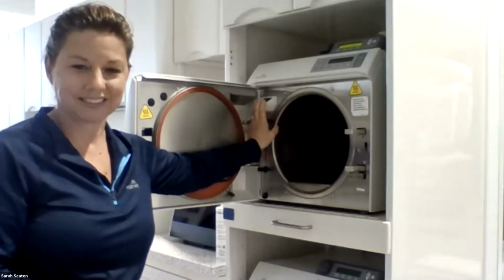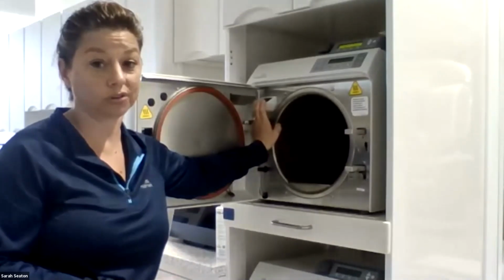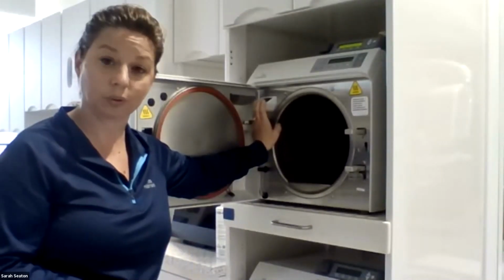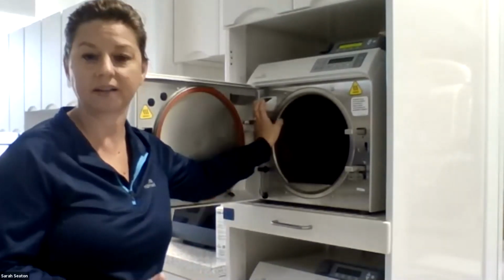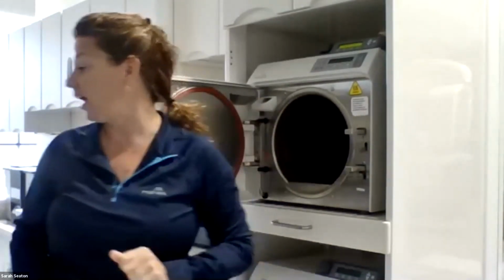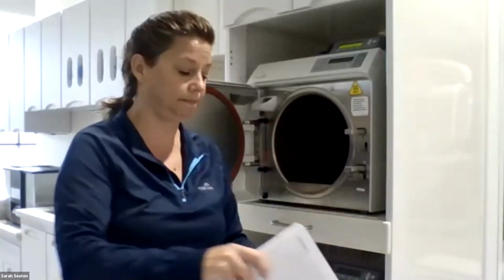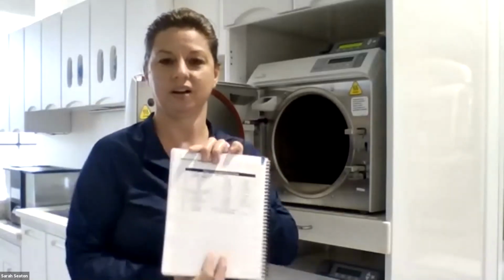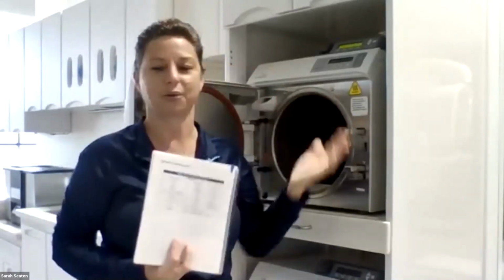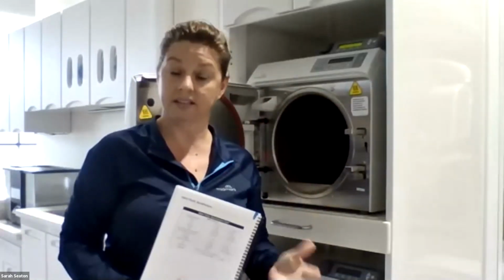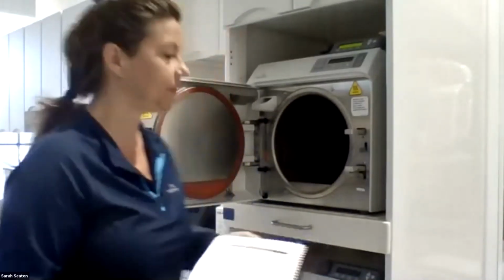Now I keep saying distilled. Distilled sometimes is difficult to come by, and it's not always feasible for every application, right? So there are alternatives, and Midmark did provide a very helpful water purity chart. It comes in your user guide, and it's right here. Can't see it real well, but that's okay. Just knowing that it's there, and you can have your water tested for the purity to know that it does fall within this guideline. If you don't have it within this guideline, you're asking for potential failures or issues, okay? That's why we provide it.